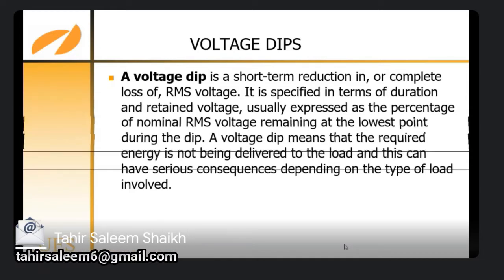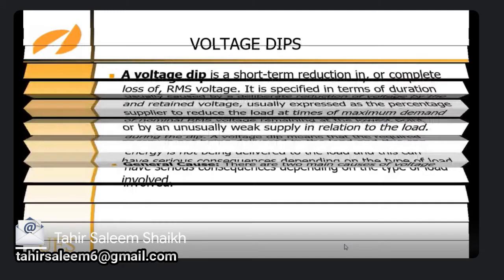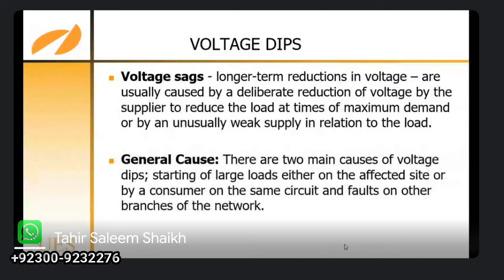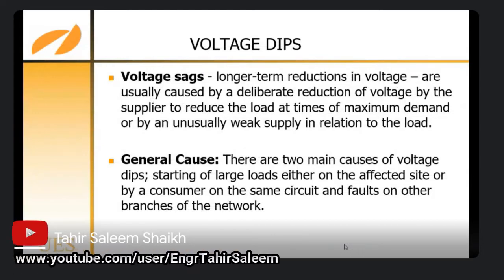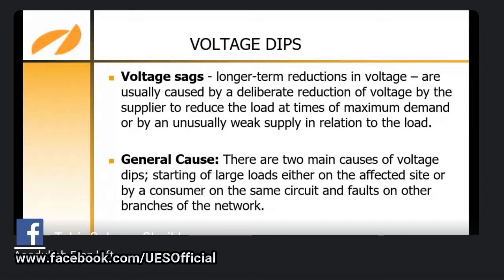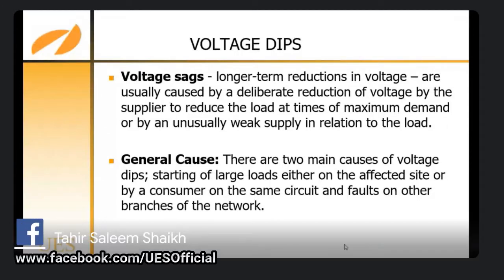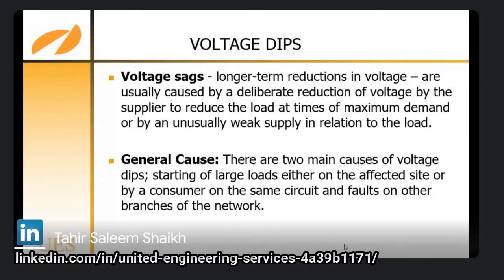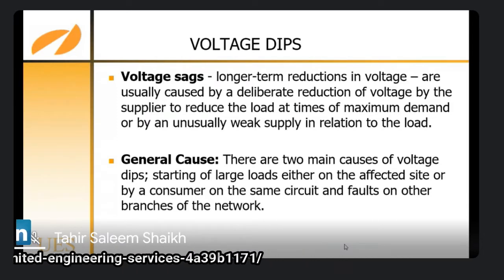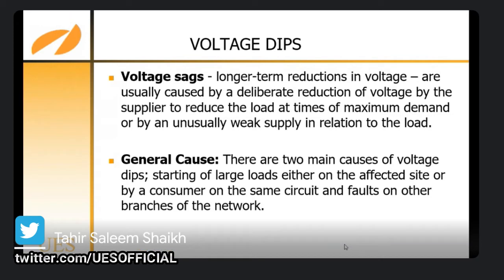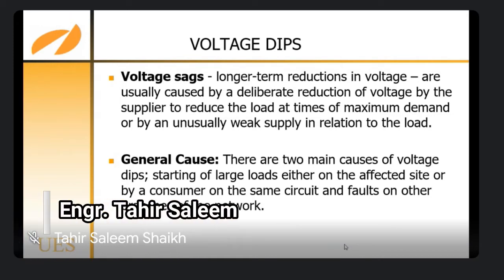Voltage sags. Longer term reductions in voltage are usually caused by a deliberate reduction of voltage by the supplier to reduce the load at times of maximum demand, or by an unusually weak supply in relation to the load. General causes: there are two main causes of voltage dips, the starting of large loads either on the affected site or by another consumer. If you start one big load like a big motor or a megawatt motor, you can experience a voltage dip.